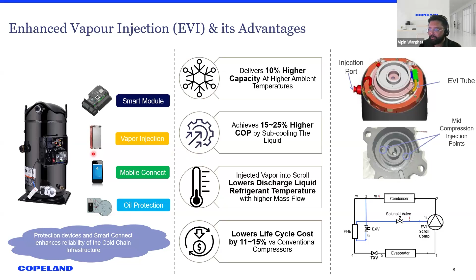All right, so let's understand how the vapor injected scrolls stand against the conventional technology in terms of life cycle cost. Let's say for 10 kilowatt of capacity, for both the conventional and vapor injected scroll, 6 units of operation have been considered, for an overall 60 kilowatt of cooling capacity of a refrigeration system. EVI based scroll would consume about 7.37 kilowatt of power for 10 kilowatt of capacity, while the conventional system will be close to 9.3 kilowatt of power input for similar capacity.